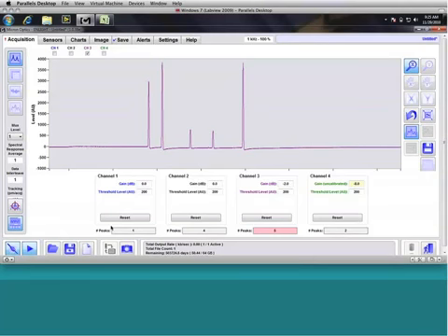One other thing I'd like to point out is the reason why peak tracking is so important. If you've used an SM130 without ENLIGHT, you know that a lot of what's done in the dynamic interrogator is done internally. So the averaging and a lot of the distance compensation are parameters that are done internal to the instrument, and the instrument has a set of indexes that it uses to apply to these settings.